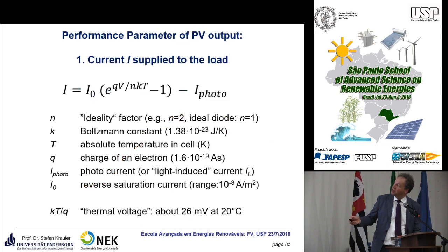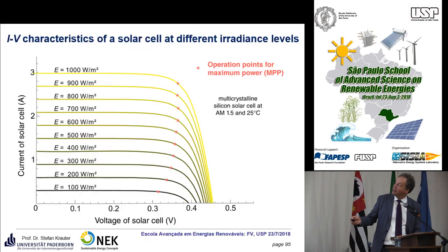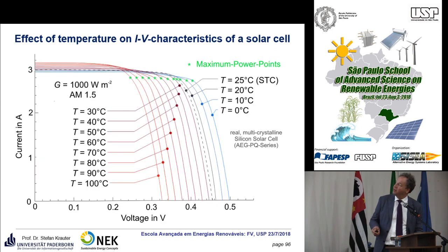And this you can see here on this curve. On that curve that you see here, for low irradiance levels we have some losses, and the maximum power point is also a bit shifted. So besides having low power output due to the irradiance level, we also have a reduction in efficiency, unfortunately. So this provides a lower efficiency than originally given. This is called the weak light effect. I will discuss and show it afterwards, what the effect of it is.